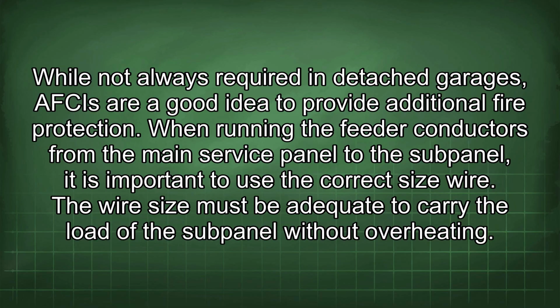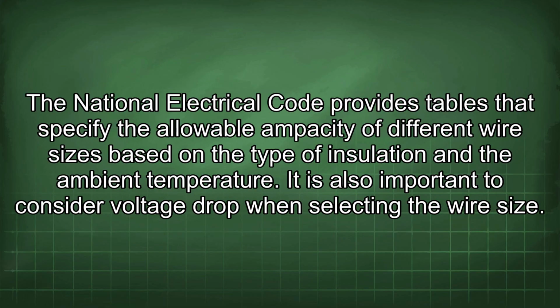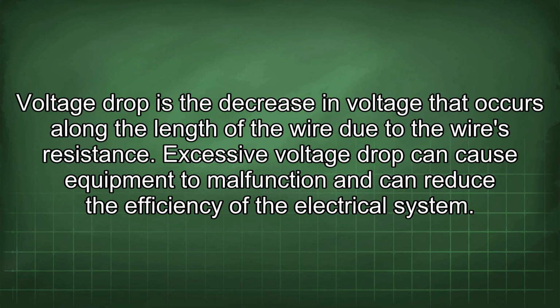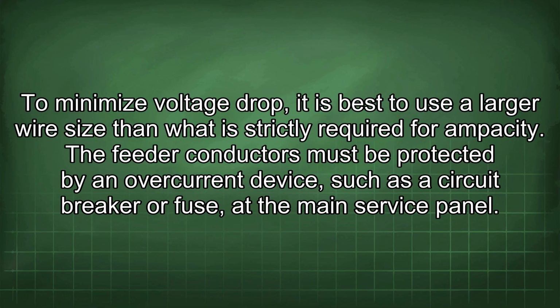When running the feeder conductors from the main service panel to the subpanel, it is important to use the correct size wire. The wire size must be adequate to carry the load of the subpanel without overheating. The National Electrical Code provides tables that specify the allowable ampacity of different wire sizes based on the type of insulation and the ambient temperature. It is also important to consider voltage drop when selecting the wire size. Voltage drop is the decrease in voltage that occurs along the length of the wire due to the wire's resistance. Excessive voltage drop can cause equipment to malfunction and can reduce the efficiency of the electrical system. To minimize voltage drop, it is best to use a larger wire size than what is strictly required for ampacity.